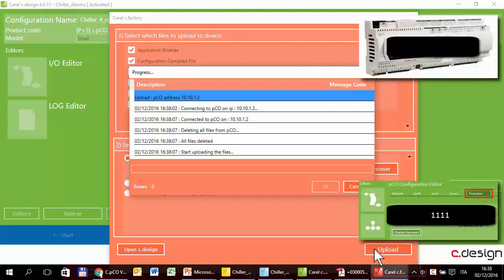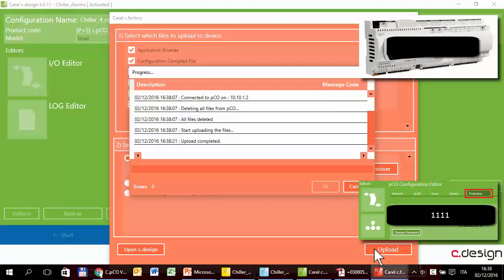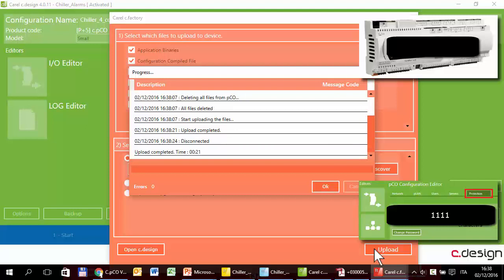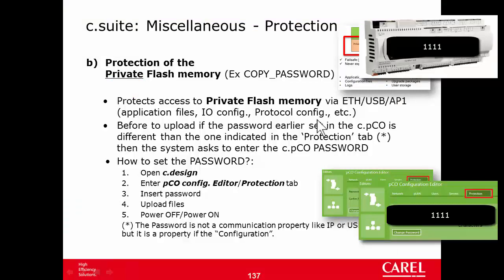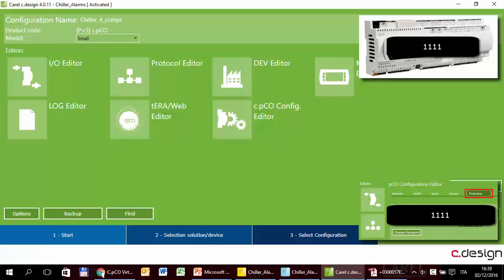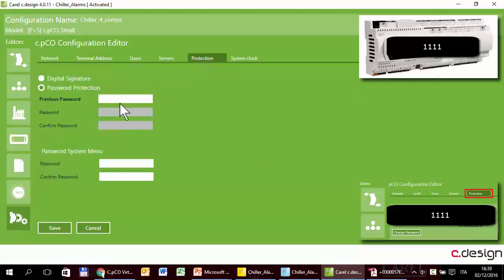In this moment the controller is not protected, so the upload starts without asking for the password. I told you before that when you upload a new configuration, we have to switch off and switch on the controller. Now we can try two possible scenarios: uploading a configuration with the same password, or with a different password. To try the first case — the same password — I can upload exactly the same configuration, because it still has 1111.